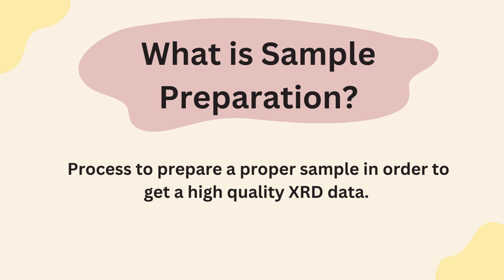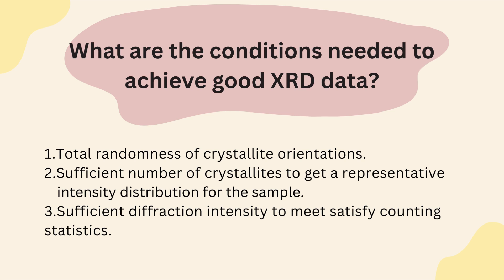What is sample preparation? Sample preparation is a process to prepare a proper sample in order to get high quality XRD data. There are three conditions that need to be achieved in order to have good XRD data: firstly, total randomness of crystallite orientations; secondly, sufficient number of crystallites to get a representative intensity distribution for the sample; and lastly, sufficient diffraction intensity to meet satisfied counting statistics.